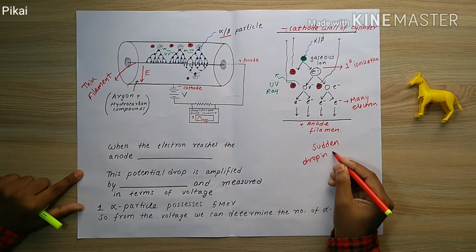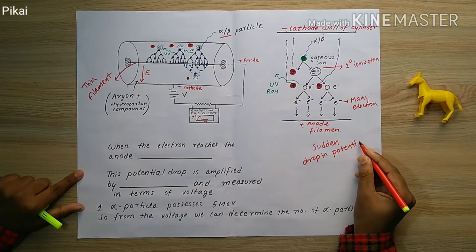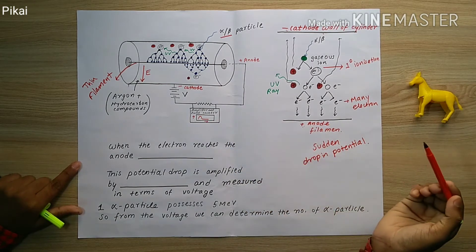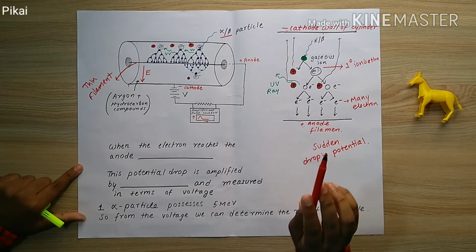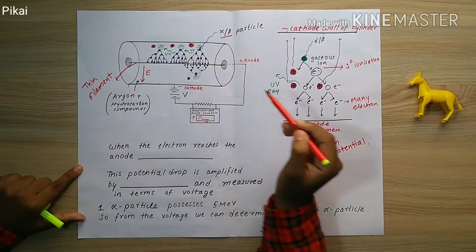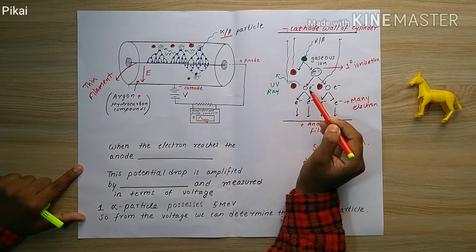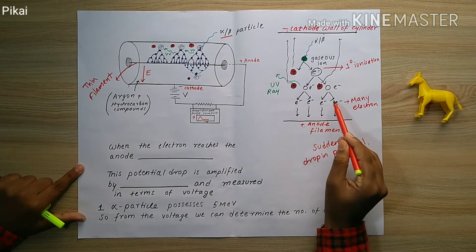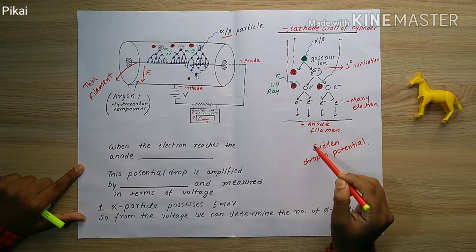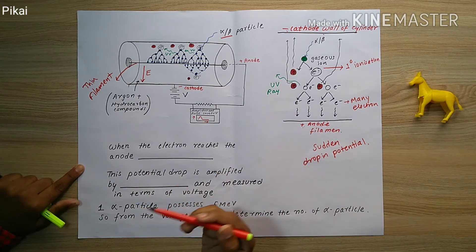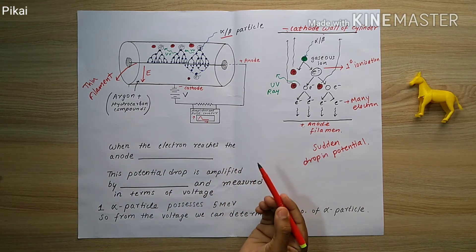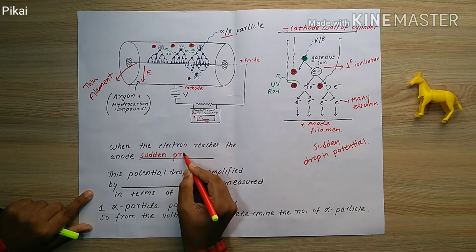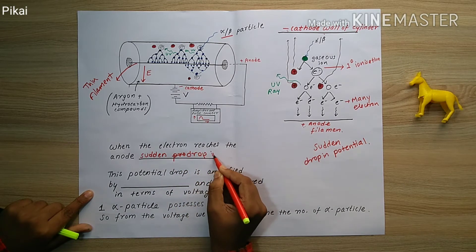When a huge number of electrons reach the positive anode filament — being negative in nature — the negative-positive interaction causes a sudden drop in the potential value. This sudden drop in potential is detected by the amplifier. The huge number of electrons interacting with the anode filament causes this sudden drop in potential, which is then measured by the amplifier.